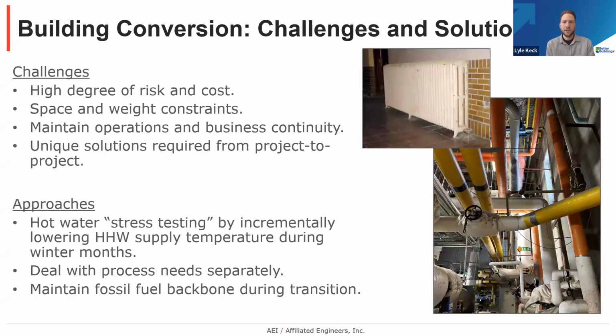Next slide, please. So some of the challenges and solutions to the building conversion aspect first. Really any type of building conversion project comes with a high degree of risk and cost uncertainty. This is messy work, it's detail-oriented work, and you often don't really know the full conditions until you begin construction. So you should be planning for schedule and cost contingencies early on with this type of work. You're also working in an existing space. There are a lot of space constraints. You might have cramped space. There might be structural limitations for placing heavier equipment, or placing equipment at all, higher up in the building or on the roof. You also may not be able to fully decommission any existing equipment until the new system is fully operational. So again, these are some common challenges. Maintaining operations and business continuity is important as well.